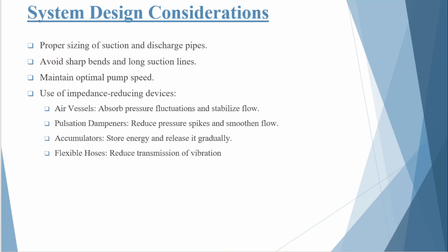Now that we've understood the causes and effects of acceleration head, the next question is, how do engineers reduce its impact in real industrial systems? The answer lies in proper hydraulic system design. The first and most important consideration is suction pipe sizing.